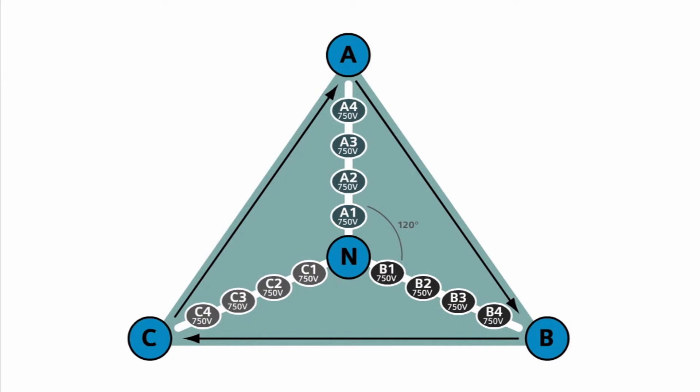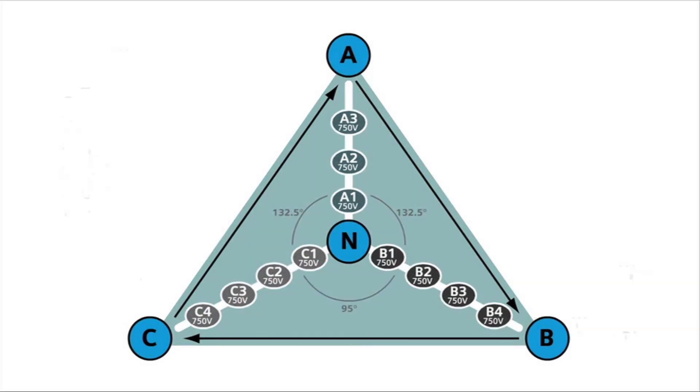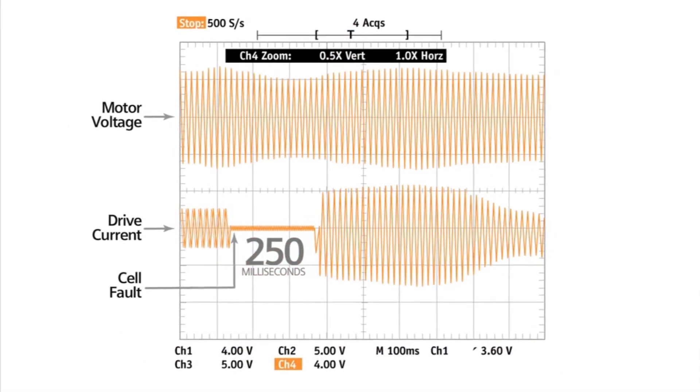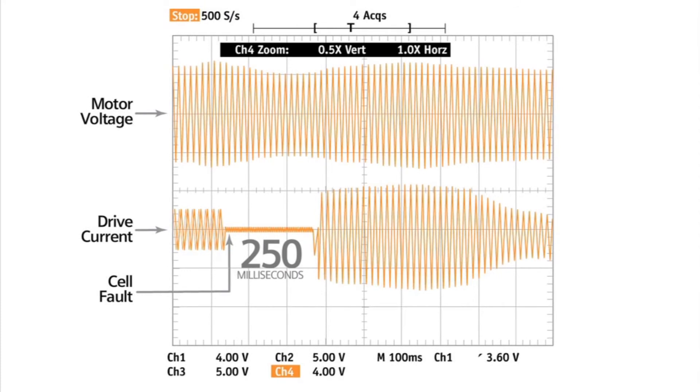Following cell bypass, the other cells remain active. The neutral point shifts in order to produce a balanced output voltage to the motor. With one cell in bypass, the drive still produces sufficient voltage for the process to continue uninterrupted. The quality of the voltage waveform remains virtually unchanged.